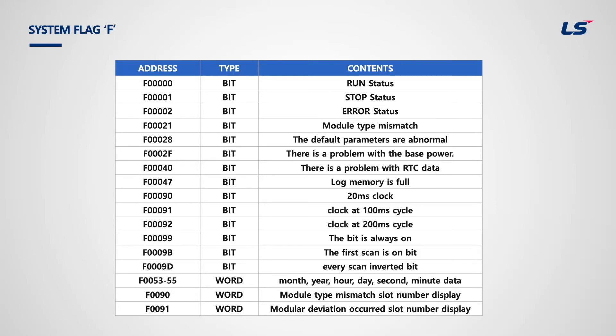F memory is a system flag area that manages the flags necessary for system operation in PLC. Flag memory is provided by the manufacturer, so users can use this memory to read the status of PLC. For example, users can check F0 bit to see if PLC is in run mode, and F91 is a 100-millisecond timer that turns the bit on every 100 milliseconds.